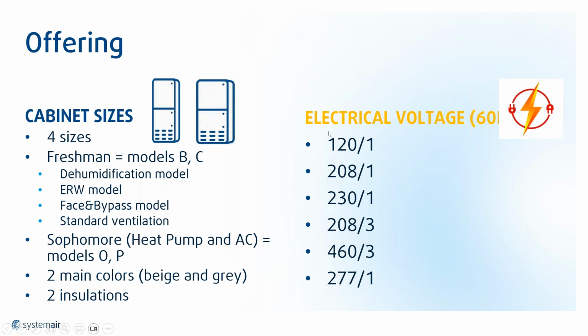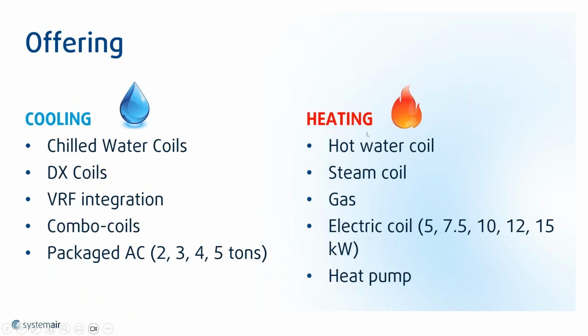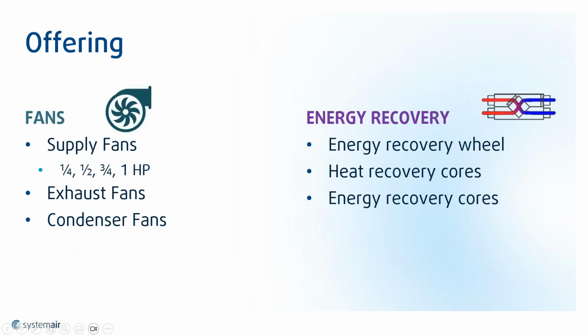It's all adaptable. So you choose any of these electrical voltages. The cabinet size, we have about 4 sizes. Cooling and heating options, and they can be mixed and matched. Keep in mind though that the steam and the gas are modules that sit on top of this 91-inch high cabinet. And then you could have combo coils, DX, chilled water, and mix it with hot water, electric elements, etc. Fans are typically selected automatically via our software based on the CFM and the statics. And then you could have powered relief as well. If you have the energy recovery wheel, you have a condenser, an exhaust fan. And if you have the sophomore, you have condenser fans. And energy recovery wheel is our preferred option, or the one we see the most. The cores are available as well, just not as, it's not a high seller.